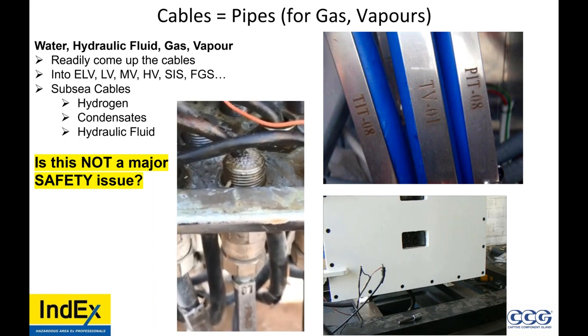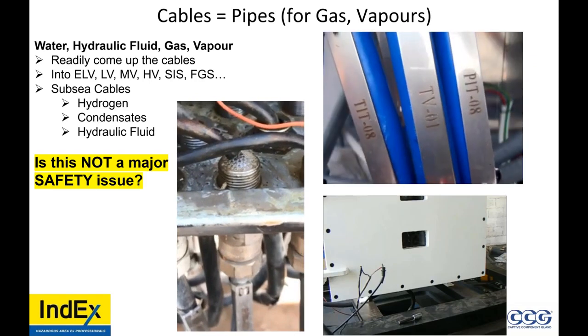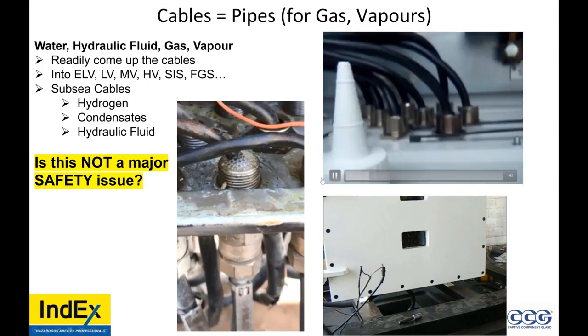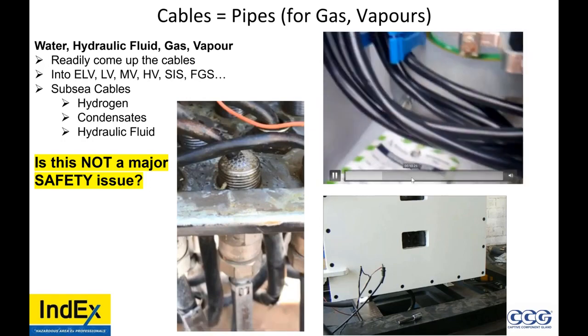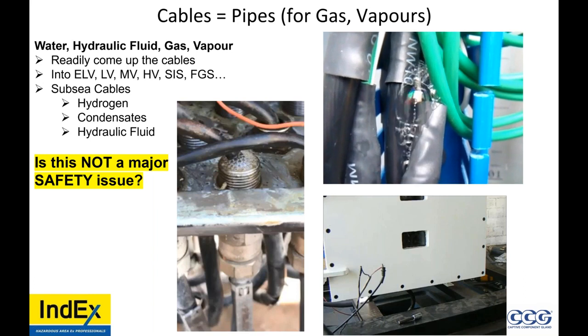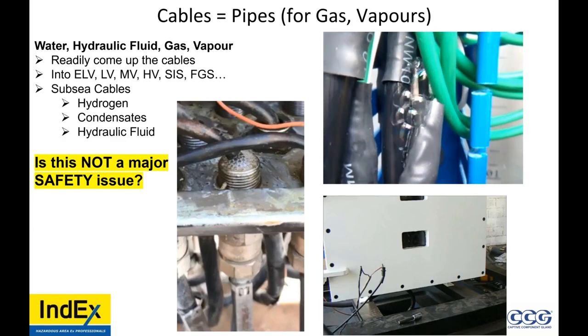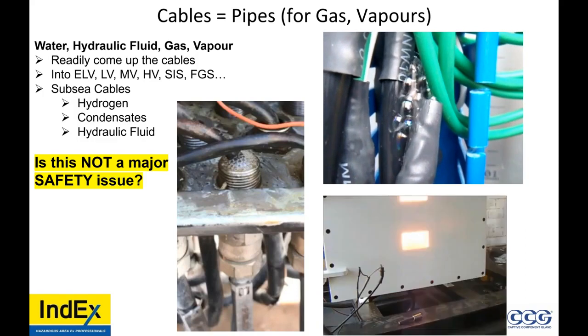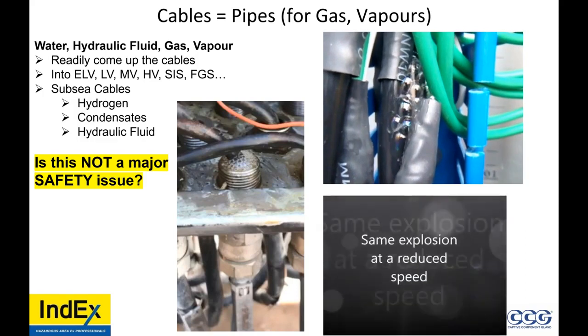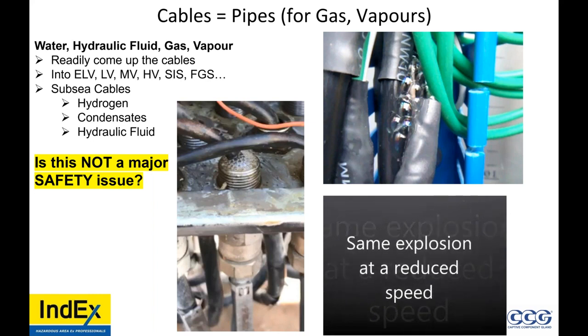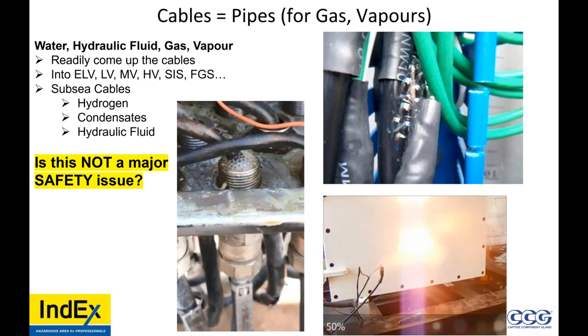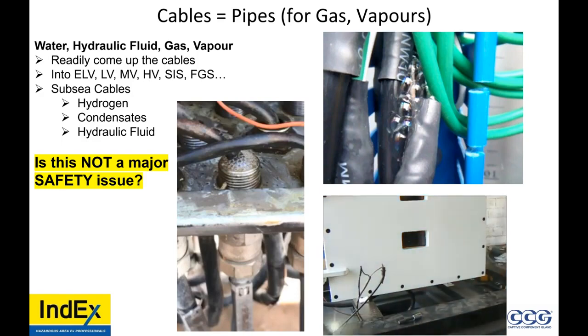See the bubbles? See the gas, maybe air coming up the cable? We don't know. Now this bottom video is a flame propagation test. An EXD explosion, where does the flame from inside the box go? The flame is going up the cable and even the individual cores.